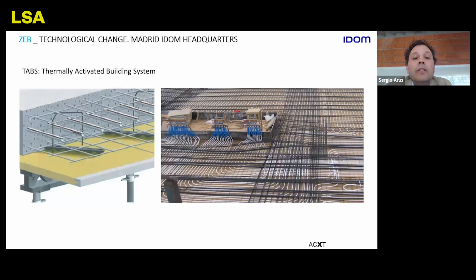The thermal mass gives you the possibility to charge the system during the night - for instance, using a cooling tower when temperatures are lower, you can charge the whole thermal mass. During the day, you just switch off the system, and it absorbs all the extra heat that people, computers and everything inside the building are creating. For winter, it's the other way around.